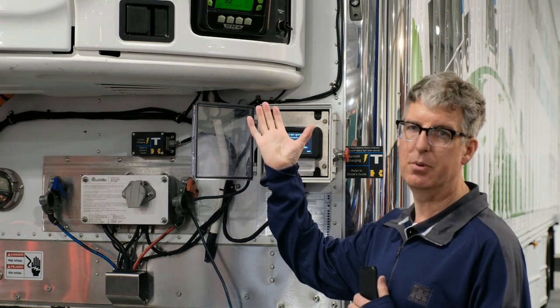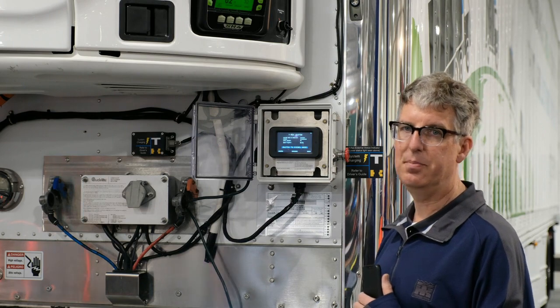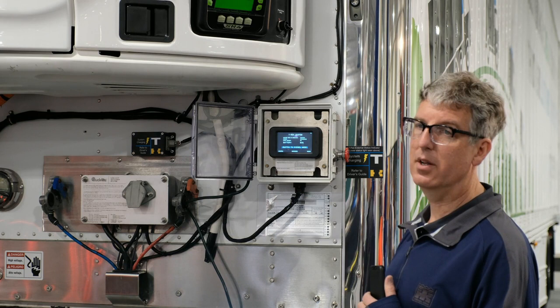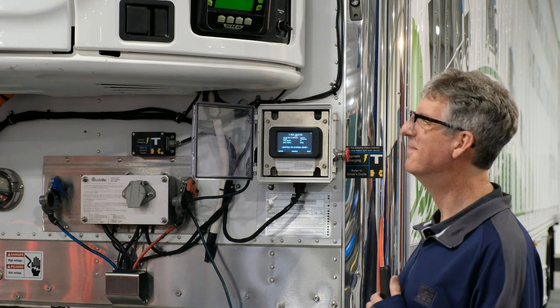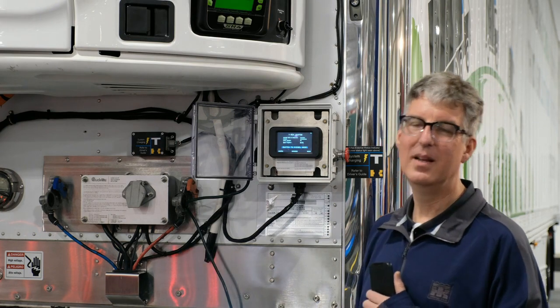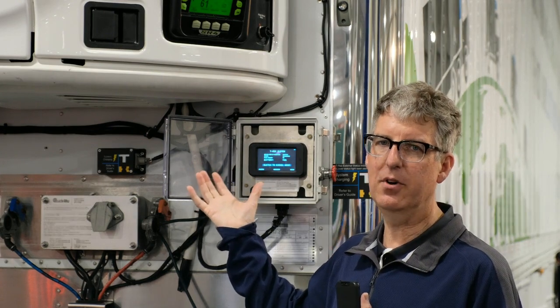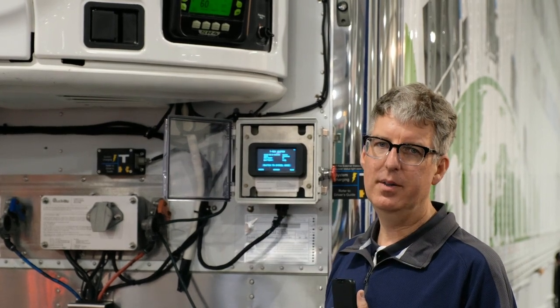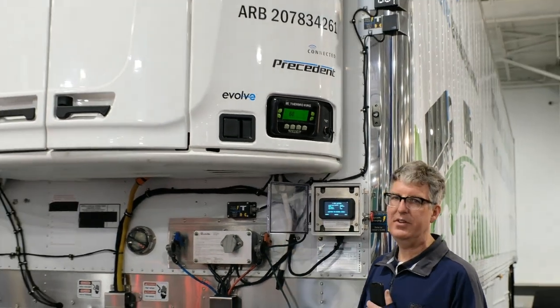This is a standard Thermo King S600, converted minimally to run off of our high-voltage power system. At this point, the starting alarm is sounded and the electric motor will start and run. The trailer refrigeration unit is now running. It's running on AC, just like you have plugged it into the grid, but it's being converted from 800 volts DC to 460 volts AC to run the standby motor.